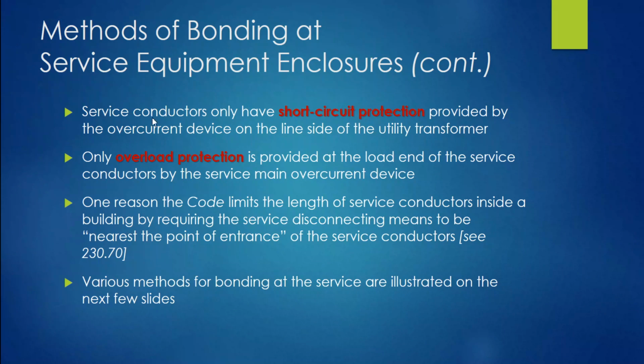Now the methods, let's look at it here. The service conductors only have short circuit protection. Again, they only have the short circuit protection to that line side utility transformer. They have overload protection, as we talked about, due to that service main overcurrent device, but that's only overload protection.